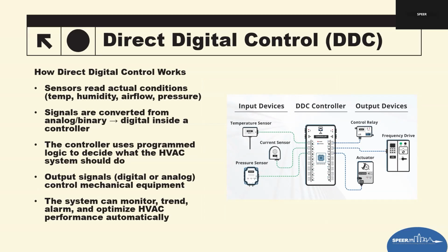Then that signal is converted from analog or binary into a digital form. These sensor signals are usually analog, 0 to 10 volt signals, or binary like off and on contacts. The DDC controller converts those readings into digital, so now it can analyze them. Then the controller uses program logic to decide what the HVAC system should do. This is where the intelligence starts to happen. The microprocessor compares sensor input, set points, run times, and the program logic sequence.